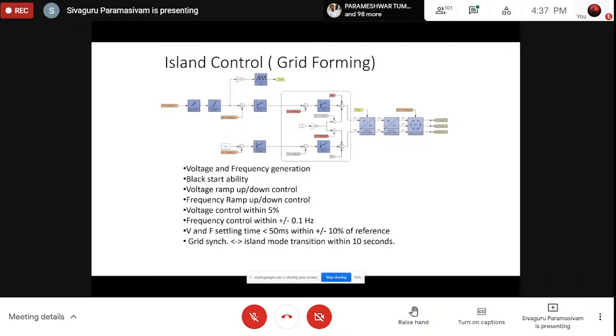The key point to note here is that it should have the black start ability. Imagine that there are so many PV modules connected to the PV inverters, but then you have a lot of transformers at the load side. Whenever we are charging the transformers, it will take an inrush current, right? Because we are charging the transformer from the secondary side. Usually the transformer's primary is connected to the grid side and the secondary is connected to the inverter side. When we are using grid forming mode, the primary side of the transformer is already off, because the grid is off. So we are charging the transformer from the secondary, and through the secondary the transformer's primary side is getting charged, and then from the primary side of the transformer, it flows to all the load networks. So here the black start ability means a smooth starting, a step starting of the transformer.